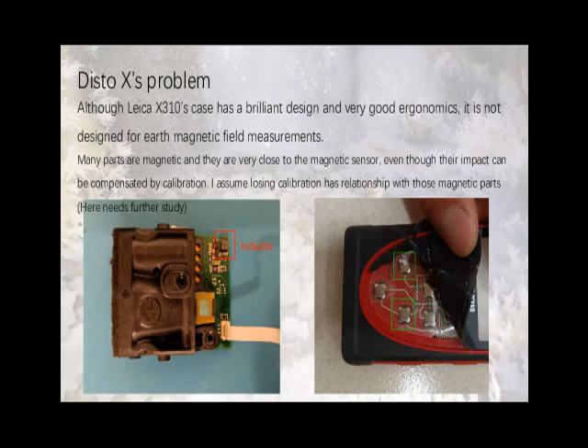If parts of the Disto X become magnetized, the device loses calibration. I assume losing calibration is related to those magnetic parts. Further study is needed, but it's not good to have magnetic parts so close to the magnetic sensor, as noted in the PNI datasheet for the RM series, RM3100 sensors.